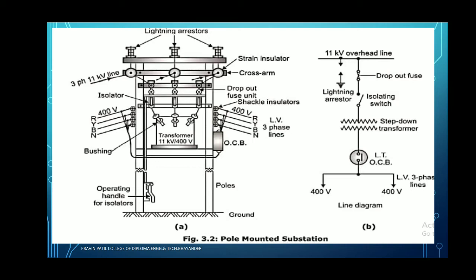Dropout fuse is connected here. The fuse is the device which provides protection from short circuit and overload conditions. During that condition, the fuse may melt out and disconnect the supply and provide protection to the healthy equipment which is connected in that substation. Isolating switch is also connected. Isolating switch is the device which isolates or connects.